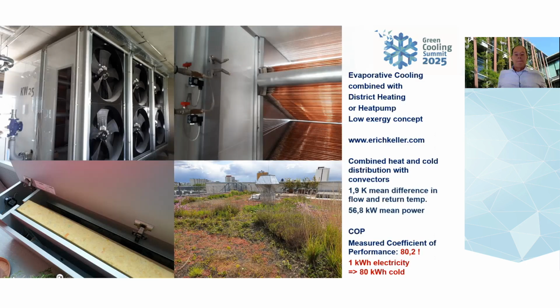Another option, no, before this one. Another option is you evaporate water directly on copper pipes. This is a concept coming from Switzerland, and I evaluate that currently in 2 buildings in Germany, in Taz Publisher and in the Böll Foundation. And here we have a measured coefficient of performance of 80. So 1 kilowatt hour produces 80 kilowatt hours of cold, and the cold water inside of the copper. So it's an open evaporation system where you evaporate water on top, and the cold water inside will cool our servers inside of this building.